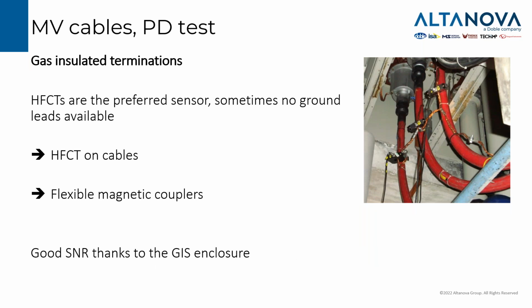If we have instead the gas insulated termination, we use HFCT on the ground lead where present. Otherwise, we have some flexible magnetic couplers to be used over the sheaths of the cable. In this specific test, thanks to the GIS design, we have a very good signal to noise ratio. So it's quite a quiet environment for testing.